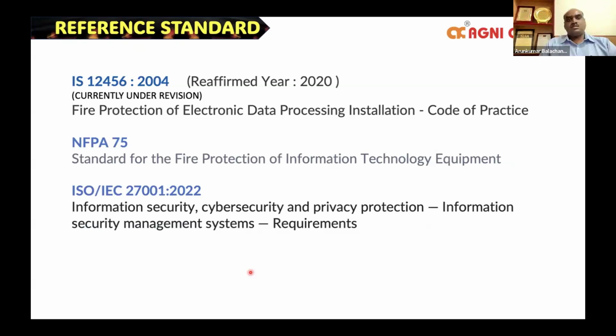Of course, fire detection and suppression will need to follow other relevant standards. For example, for detection, we need to follow IS 2189 and NFPA 72 or EN 54. And for suppression, we need to follow either IS 15501 or NFPA 2001.